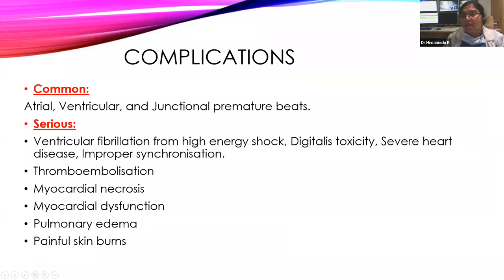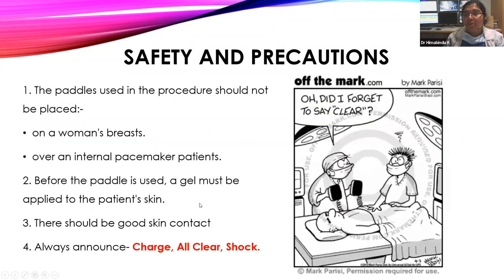Complications: common complications include atrial, ventricular, and junctional premature beats. Serious complications include ventricular fibrillation — especially with digitalis toxicity, severe heart disease, or improper synchronization — thromboembolism, myocardial necrosis, myocardial dysfunction, pulmonary edema, and painful skin burns. Safety and precautions: do not place paddles on a woman's breast or over an internal pacemaker; always use conductive gel for good skin contact; always announce 'charge, all clear' before delivering shock.